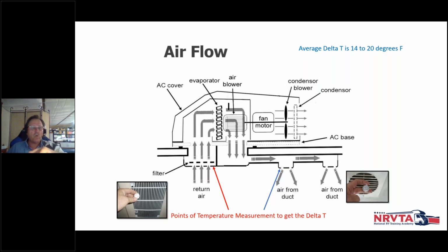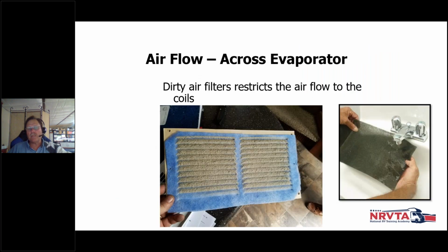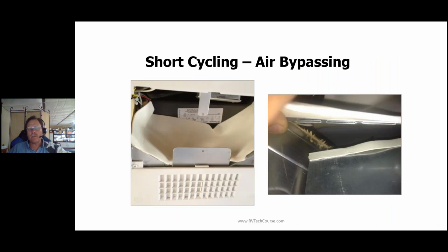So now we've got cool air coming out of the evaporator, getting sucked back on the other side. Pretty soon it begins to short cycle, and it doesn't allow us to cool the compartment where the human is, because we're just moving the air out one side and sucking it back in on the other. It's all because that divider in the plenum is not blocking like it should.